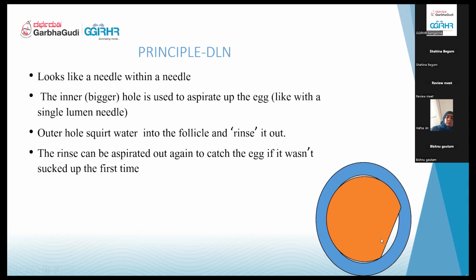There is no connection between the two. If you cut the needle of the double lumen, this is how it will look. Into this lumen, the aspirated fluid goes. From this lumen, the flushing takes place. It looks like a needle within a needle. The diameter of the double lumen is also 0.8, 17 gauge. Yes, it will come to 17 gauge only. The inner bigger hole is used to aspirate the oocyte, and the outer smaller one is used to rinse or flush the follicle. The rinse can be aspirated out again to catch the oocyte. If you have missed it the first time, because of flushing it gets aspirated.